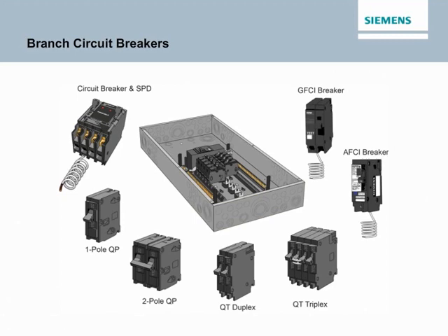Residential circuit breakers are typically one-pole, two-pole, or three-pole breakers with current ratings of 225 amps or less and voltage ratings of 120 volts, 120/240 volts, or 240 volts. Because residential circuit breakers are also used in some commercial applications, and many commercial applications require three-pole breakers, some three-pole breakers are also included in this category.